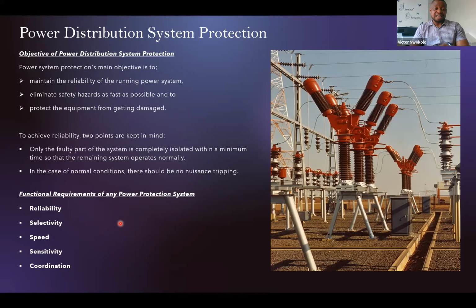The other thing to consider is selectivity. The system should have the ability to avoid unwarranted trips, like what I mentioned earlier. So it should be able to only isolate the part of the power system that is faulty or where the fault occurs. Then also it should have speed, and it should be able to operate within a specified time in order to avoid damage. And two, it should be able to know when to operate. That is something it must consider as being sensitive.